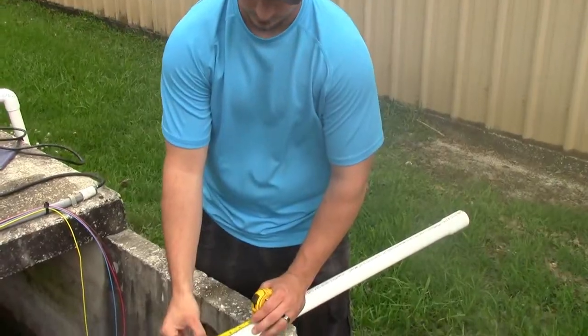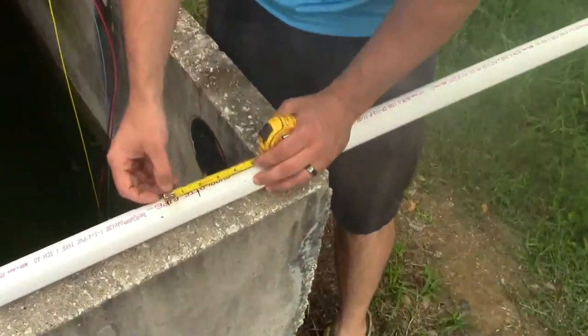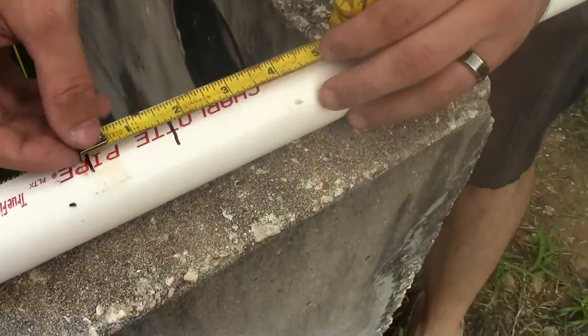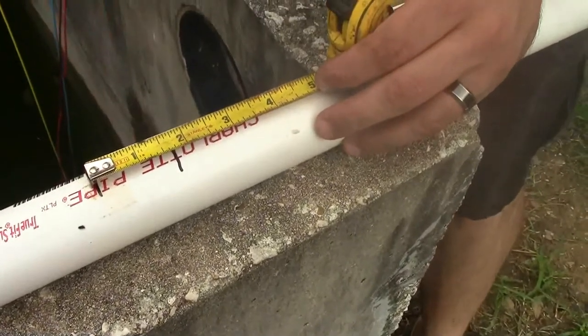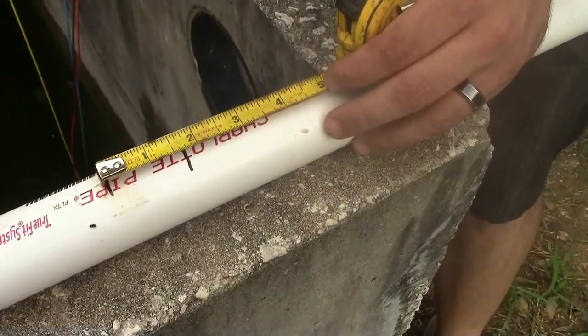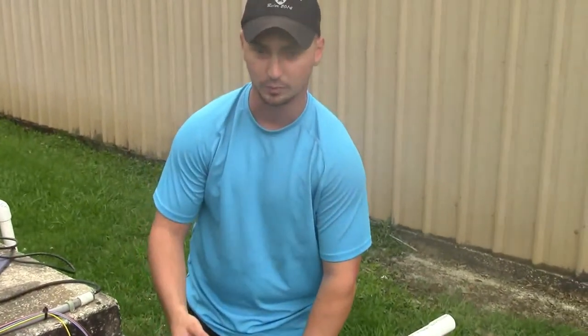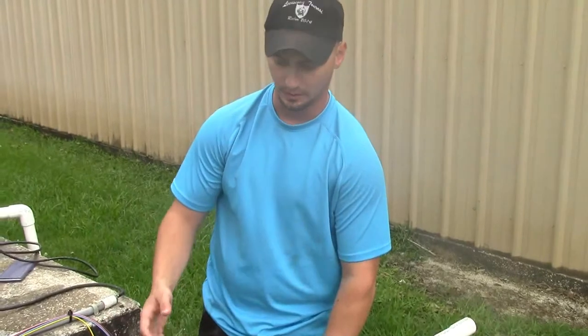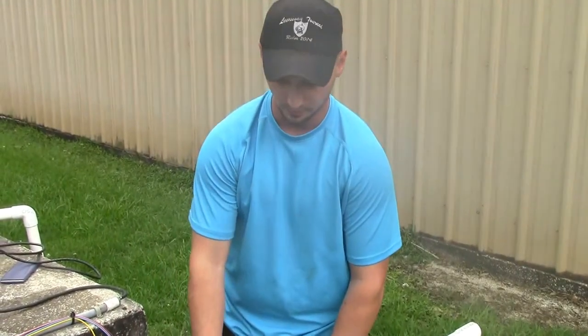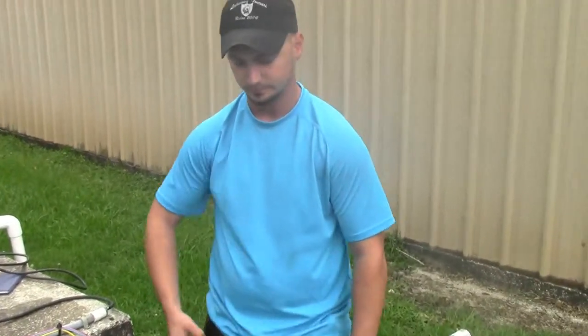And we're rolling. Okay, right here, what we're doing, we're measuring the height drop and elevation of water. And we're going to take this number, multiply it by our cross-sectional area of the tank, and that's our volume that we used. And we're going to divide it over the time, and that's how we get our volumetric flow rate of our pump.